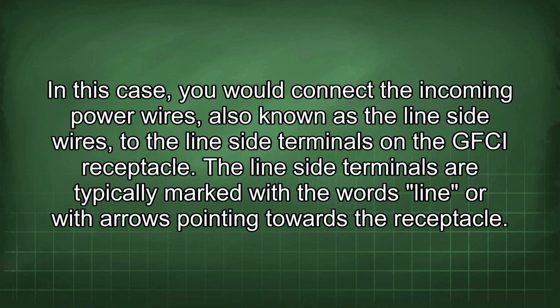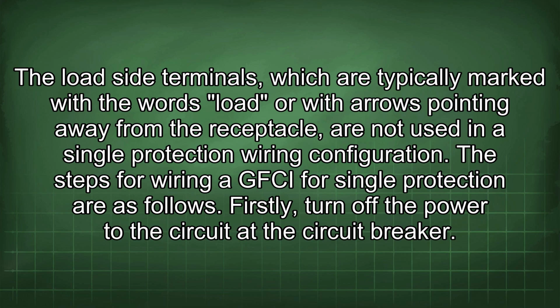In this case, you would connect the incoming power wires, also known as the line-side wires, to the line-side terminals on the GFCI receptacle. The line-side terminals are typically marked with the word line or with arrows pointing towards the receptacle. The load-side terminals, which are typically marked with the word load or with arrows pointing away from the receptacle, are not used in a single protection wiring configuration.